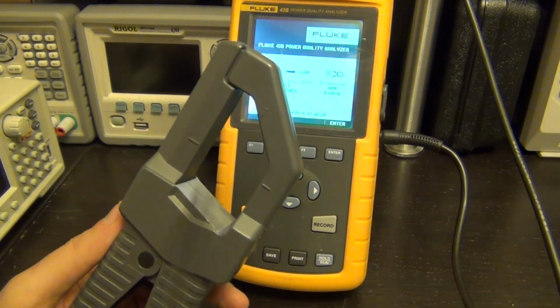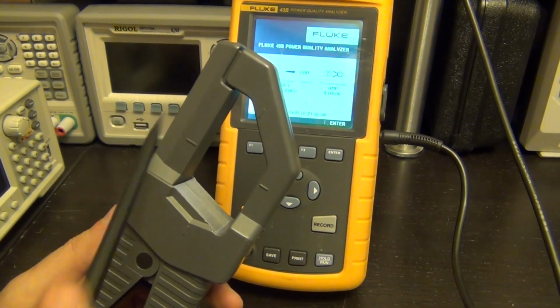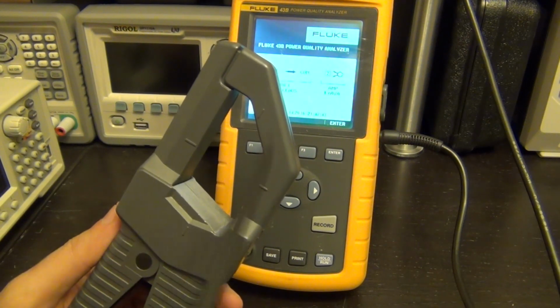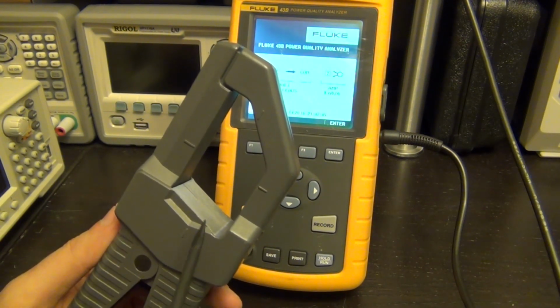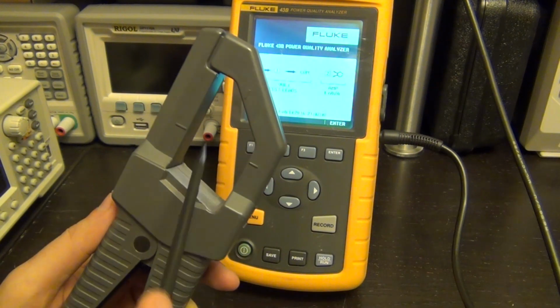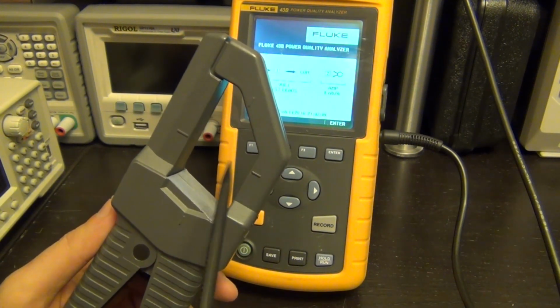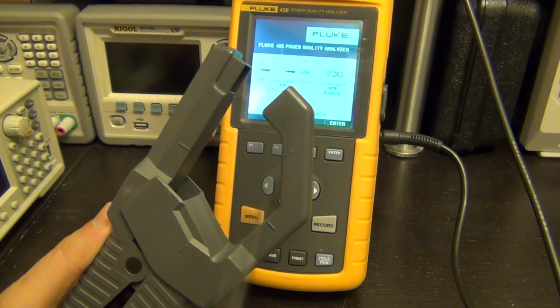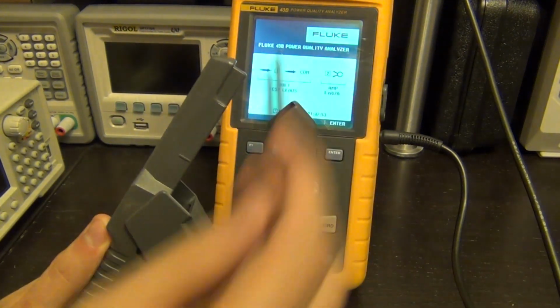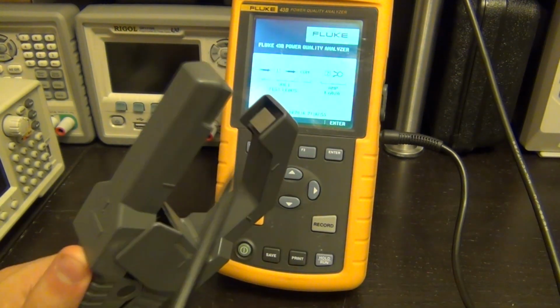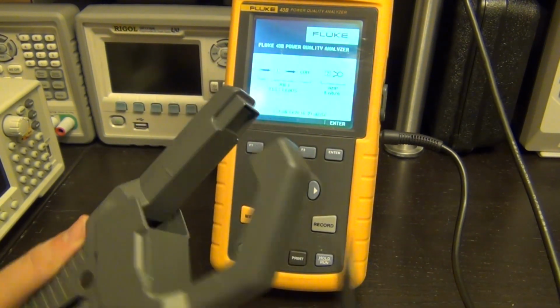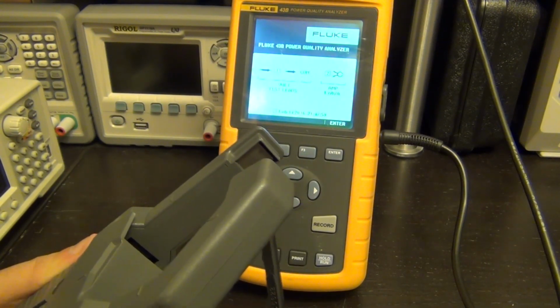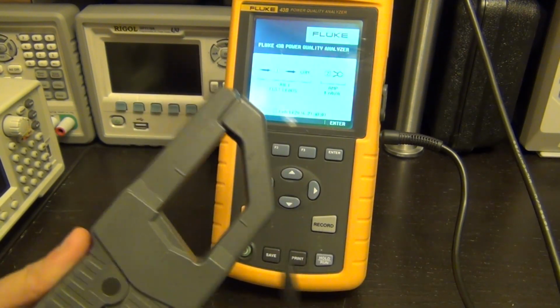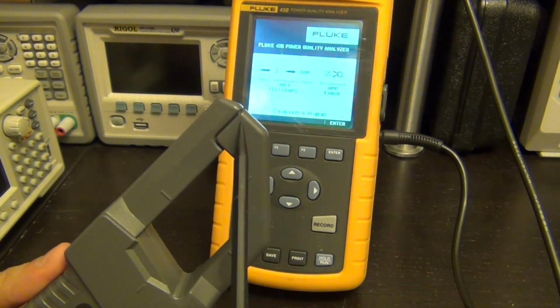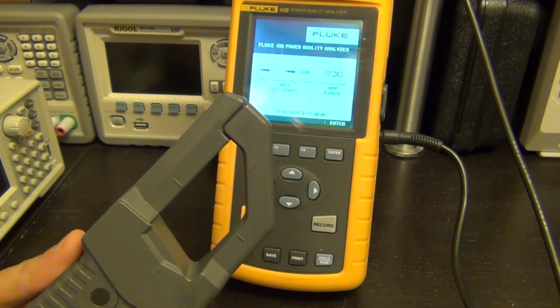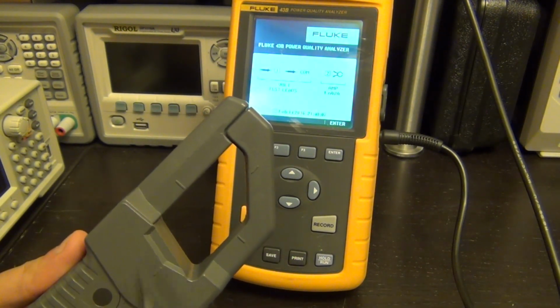Now, obviously, the best type of pickup is a nice continuous metallic round around the wire, but we can't do that because then nothing can be put through it—you'd have to cut the cable. That's why they make a compromise and make a clamp such that you can open it, slide the wire in, and then close it. You can see we have metallic pieces here and here, nice and clean and shiny, very flat surfaces, so that when you close them they make a very good connection, essentially emulating what is almost a closed loop completely.